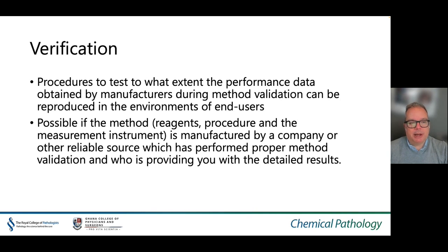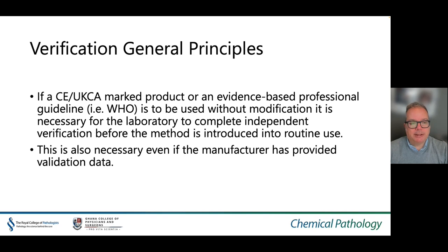You should also validate methods following a major change to previously validated parameters of the equipment, for example IT changes, software or method updates. Verification of procedures tests to what extent performance data obtained by the manufacturer during validation can be reproduced in the environment of the end user. If a CE/UK CA marked product, FDA approved product, or an evidence-based professional guideline from the WHO is to be used without modification, it is necessary for the laboratory to complete an independent verification before the method is introduced into routine use. This is also necessary even if the manufacturer has provided validation data.